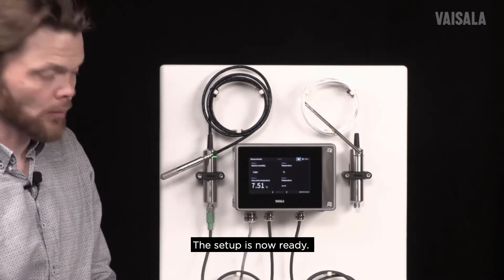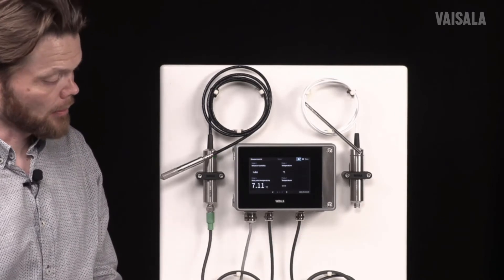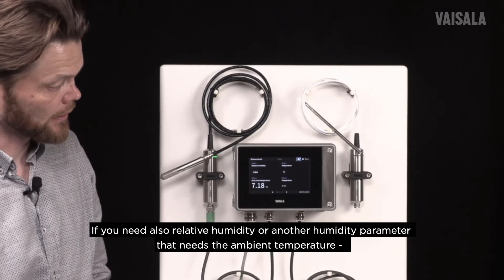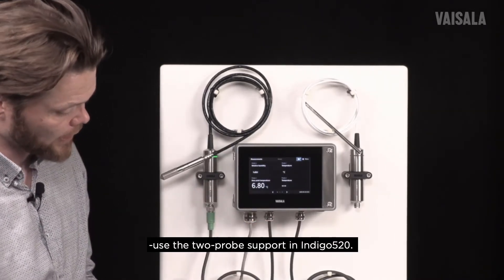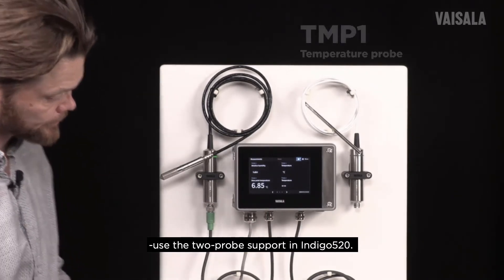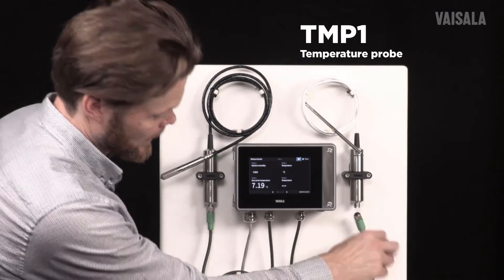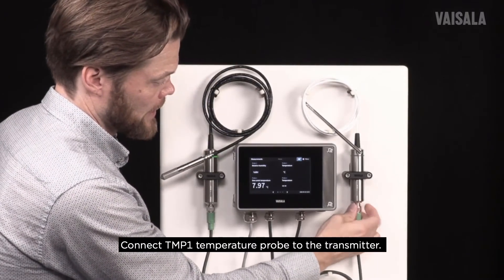If dew point temperature is what you want to measure, this setup is completely fine. But if you also need relative humidity or some other humidity parameter that requires the ambient temperature, we can use the two-probe support that the Indigo520 has. For that I have a TMP1 temperature probe — let's connect it to the transmitter.